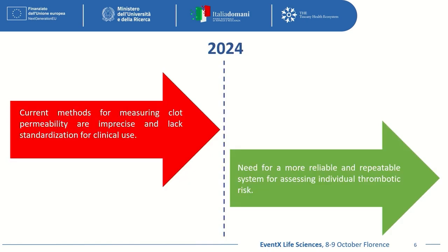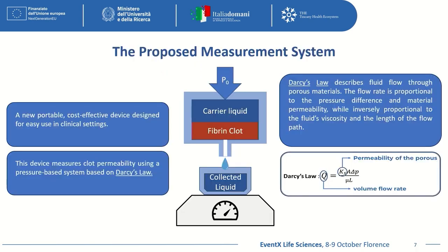Current methods for measuring clot permeability are imprecise and lack standardization for clinical use. We need a more reliable and repeatable system for assessing individual thrombotic risk. For this reason, we've proposed a new portable, cost-effective device designed for use in clinical settings. This device measures clot permeability using a pressure-based system based on Darcy's law.